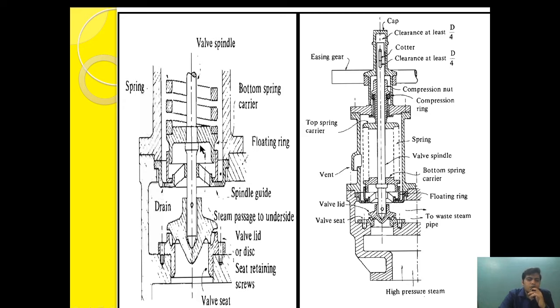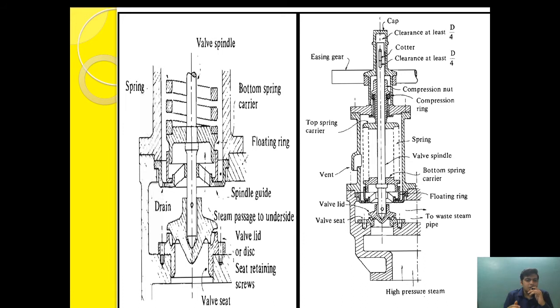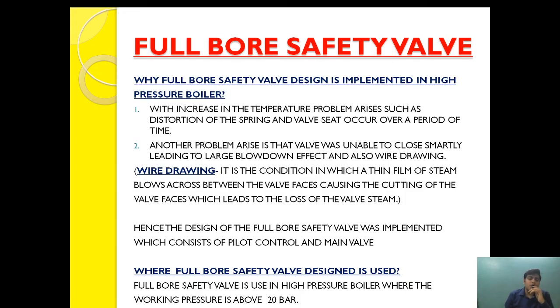The design of the improved high-lift safety valve overcame this problem, but still some amount of blowdown effect remained. Blowdown effect means that after the design pressure is reached, steam is still escaping from the safety valve causing loss of steam while the valve is seating. The valve was designed to lift at 3% above working pressure, but when sitting it should close just at or just below design pressure. Due to blowdown effect, it used to sit at a much lower steam pressure.